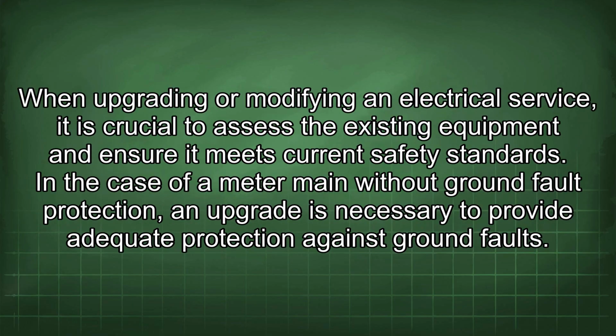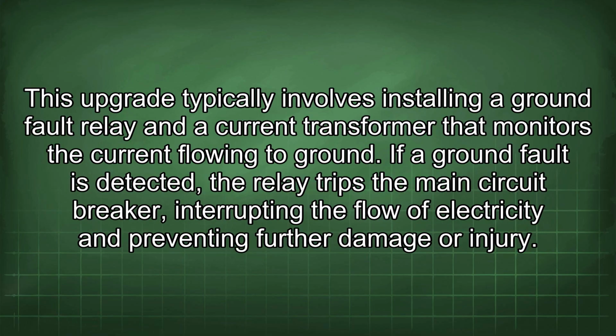When upgrading or modifying an electrical service, it is crucial to assess the existing equipment and ensure it meets current safety standards. In the case of a meter main without ground fault protection, an upgrade is necessary to provide adequate protection against ground faults. This upgrade typically involves installing a ground fault relay and a current transformer that monitors the current flowing to ground. If a ground fault is detected, the relay trips the main circuit breaker, interrupting the flow of electricity and preventing further damage or injury.